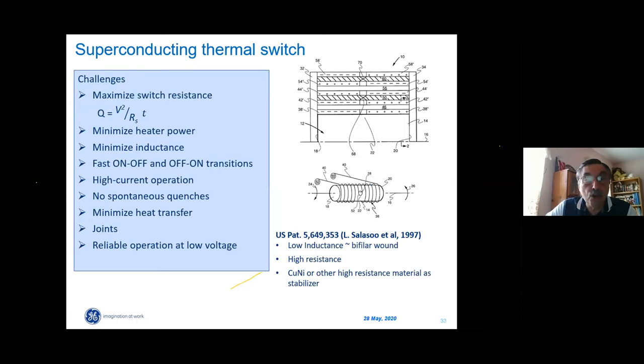Another know-how is the switch. The advantage is the switch resistance. What we want is minimum losses during ramping. The switch is the highest source of losses during ramping of the magnet. So we want the switch resistance as high as possible when we ramp the magnet. The way to do it is basically make it larger, but it's very difficult and expensive. So we try to find the best compromise.